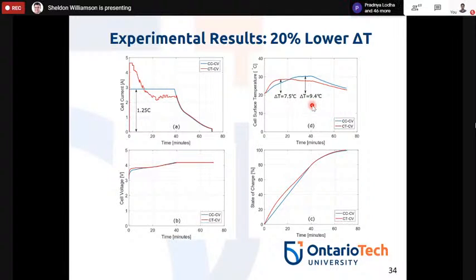So the BMS that I showed you earlier is so important. This algorithm should be fed into the BMS so you can keep temperature under control, such that the catastrophic effects from capacity fade do not occur, since once capacity fade occurs, as you saw, a short circuit can occur.